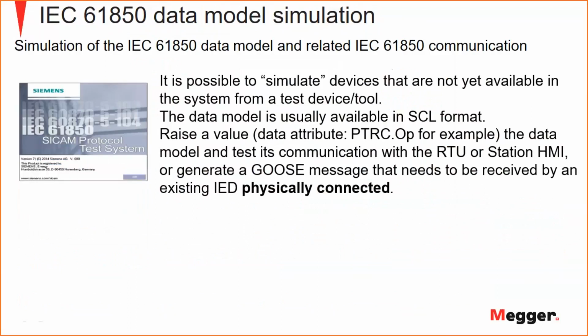For the data model, as I said, we can simulate devices from the SCL file. There are many tools that are able to do that. Usually, these tools are related to manufacturers that provide the SCADA systems because they require a certain SCADA competence to do that. And here I have a Siemens SICAM. There is a reason why I have a Siemens here in this presentation. You will understand that. So as I said, we can simulate the messages sent by the device without having the device. And yes, the PTRC is a protection trip.